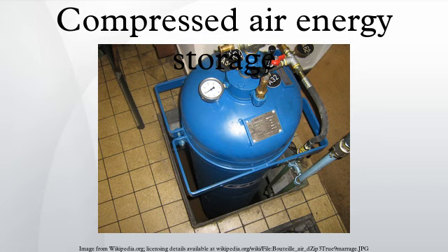This configuration improves the energy density of the storage system, because all the air contained can be used. It improves the efficiency of the turbomachinery, which will work under constant inlet conditions. It also opens the way to the use of different geographic locations for the positioning of the CAES plant. On the other hand, the cost of this storage system is higher, due to the need of positioning the storage vessel on the bottom of the chosen water reservoir and due to the cost of the vessel itself.